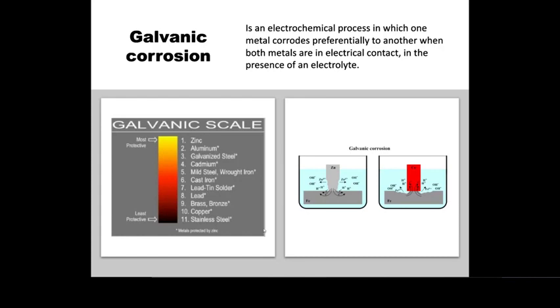So, for example, sometimes this is actually used intentionally to make things last longer. A mild steel hot water cylinder, you've got an enamel-lined mild steel, which, if just left normally, would rust. So the enamel protects it, it's like a paint coating on it. That's your first stage defense. But also inside it, it's got a zinc anode, which looks basically like a shaft of dull grey metal bolted to the top of it. What happens is that zinc actually loses particles, it's losing electrons, which help protect the steel. So it starts to break down, keeping the steel intact.